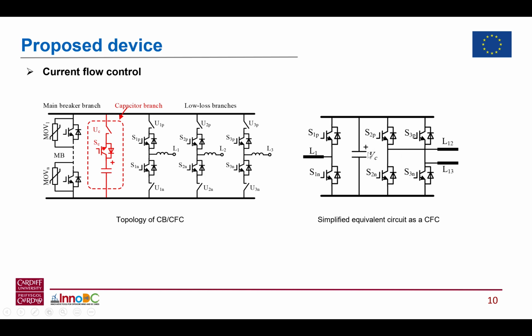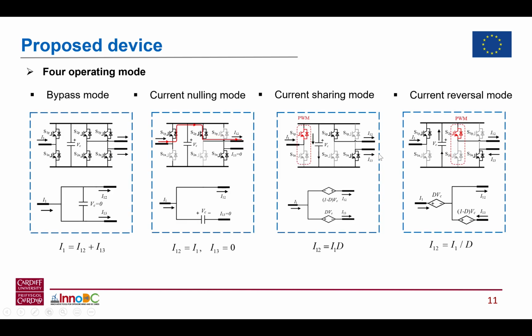So it's a half-bridge based CFC controller. And for such a controller, we have four operating modes. For the bypass mode, all the switches are switched on, so the CFC controller will have no influence on the current flows in the systems. In the current blocking mode, we insert the capacitor into one of the transmission lines, so the current will just flow in one of the transmission lines, but the other is zero.